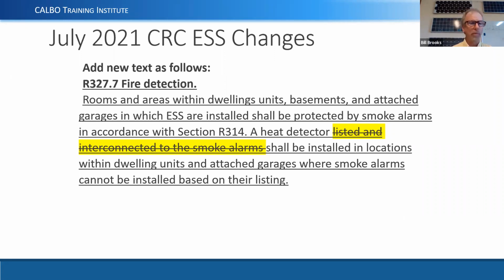There are a few products on the market that will probably do the work. There's a lot of folks kind of scratching their head on this one. So if it's on the outside of the garage, you would not need this. If it's on the inside of the garage, then it may have to be addressed. If the garage never gets above 105 degrees, which in some places in California is true, then a smoke alarm would be acceptable. So smoke alarms are not completely disallowed in garages. It just can't be super hot and it can't be super cold. And hey, California's a great place, so why not?